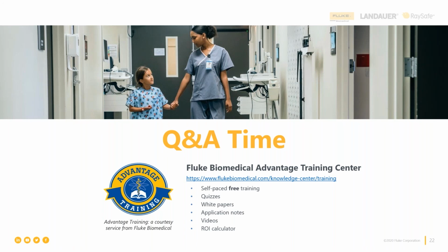And working very closely with the infection control staff is also critical to high confidence in your biomed department. It shows, number one, you care. Number two, you're interested in and engaging with them so that they can achieve the reduction of cross-contamination and nosocomial infection within the hospital. So the policies of the hospital are important that you follow, and the user manual recommendations about how to clean the device, whether it's the test instrument or the medical device, are also critical. Central processing needs to have been instructed on how to clean the medical devices, but you do too. And then your test instrument is up to you, and we provide you that information in the user manual. Don't forget your filters on your ventilator analyzers. Please use your pre-filter. If you suspect it's dirty, get a new one. Yes.